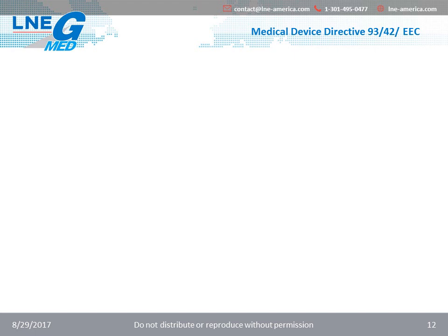The European regulations address the usability requirements in order to minimize and reduce use errors and use-associated risks in general essential requirements of medical device directives. Here we will review requirements of the Medical Device Directive 93/42/EEC. You can find requirements of the IVD directive in the newsletter published on the GMED NA website.